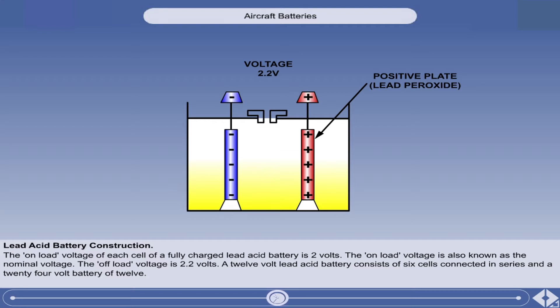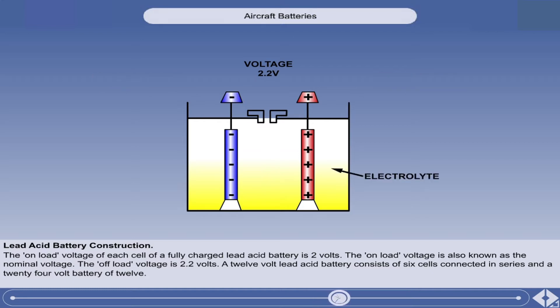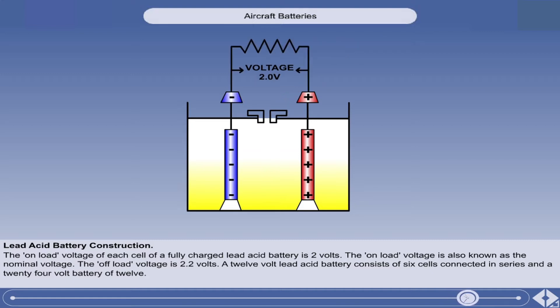The active material of the positive electrode, or plate, is lead peroxide, and that of the negative plate is spongy lead. Both plates are immersed in an electrolyte solution of water and sulphuric acid. The liquid level should be just above the top of the plates. The container is glass, or more usually hard plastic, with a filler cap to allow topping up with distilled water to replace water lost through evaporation during use. A vent hole in the cap allows the escape of hydrogen gas, which is produced when the cell is working.